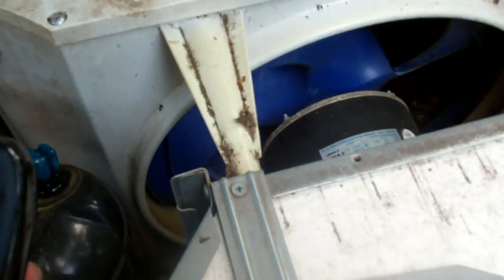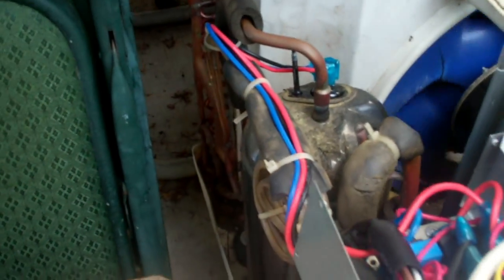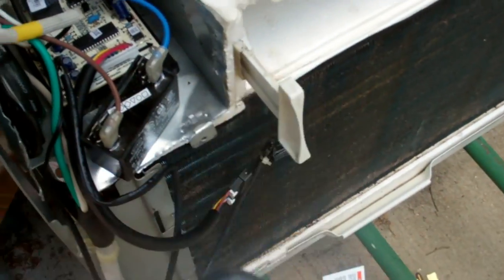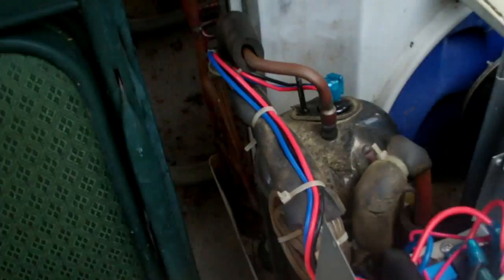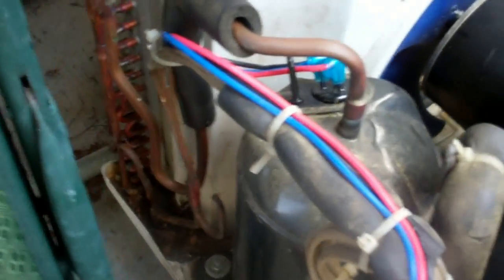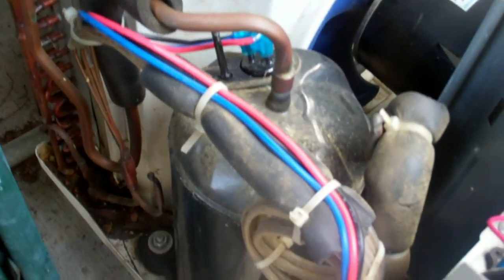There's nothing wrong with the fan. The fan kicks on, there was not an issue with it. It spins, it's not locked up. As soon as I turn the power on with the remote control here, the fan kicked on, it would blow cold air. But again, the compressor was stuck on and I tried to turn this thing off. Everything turns off but the compressor stays on.